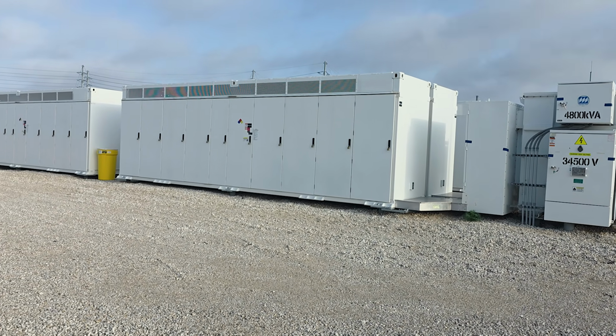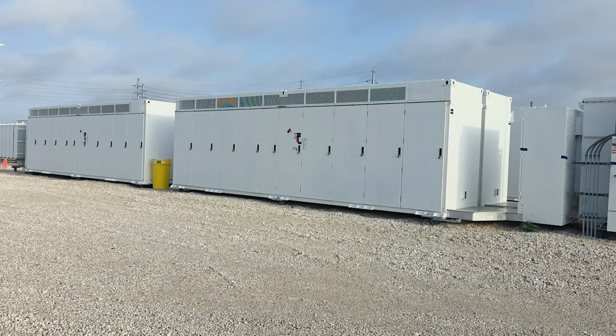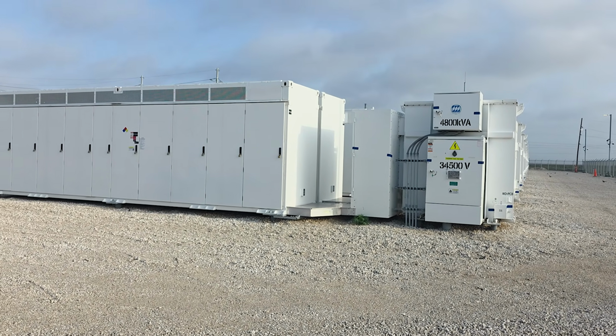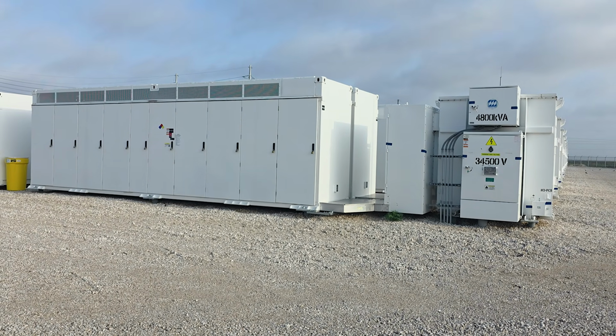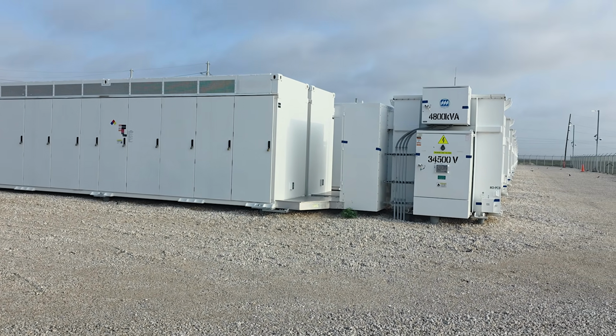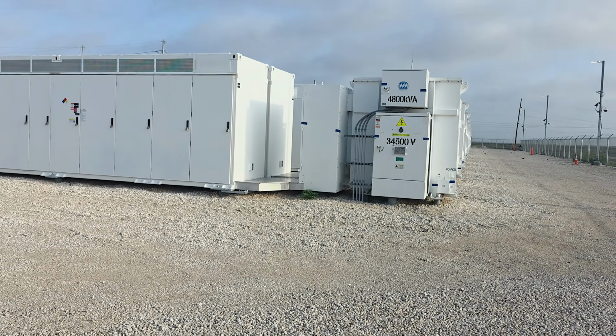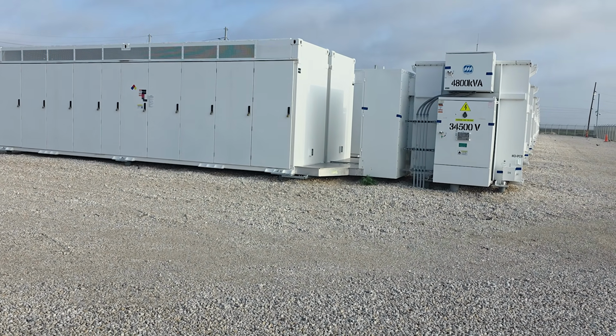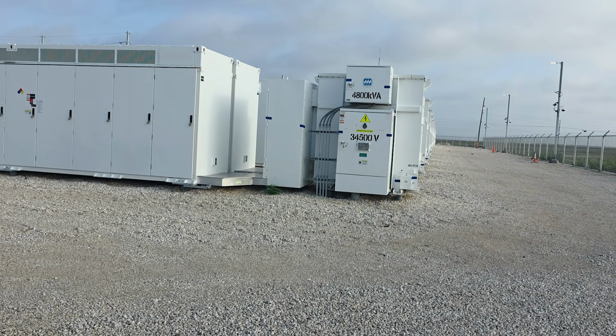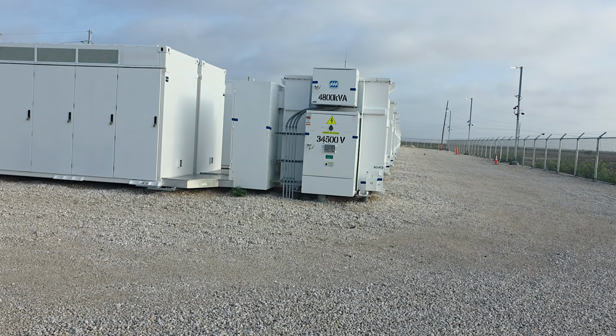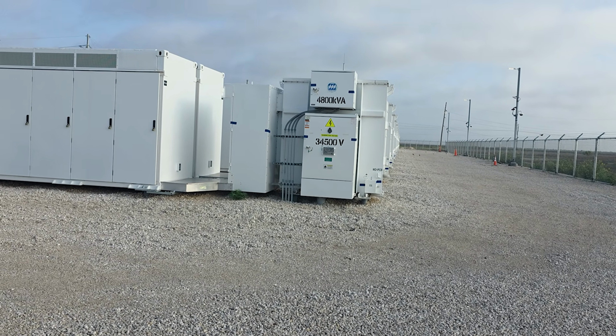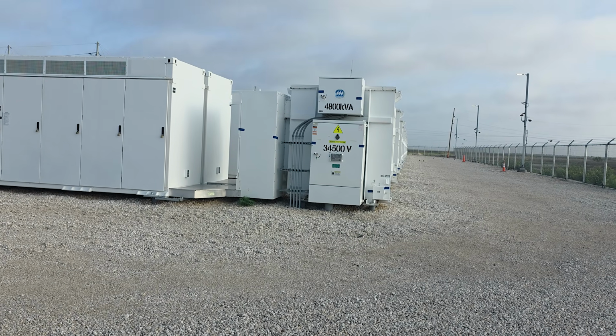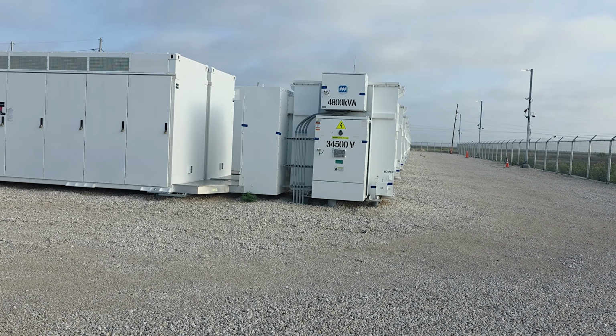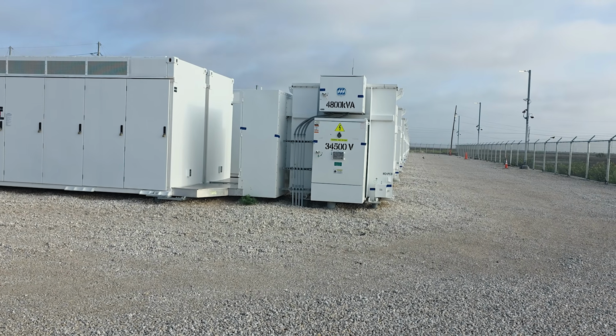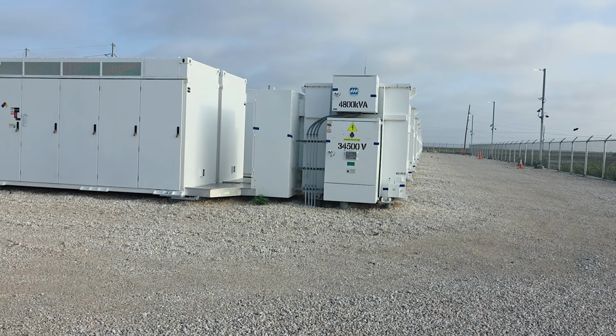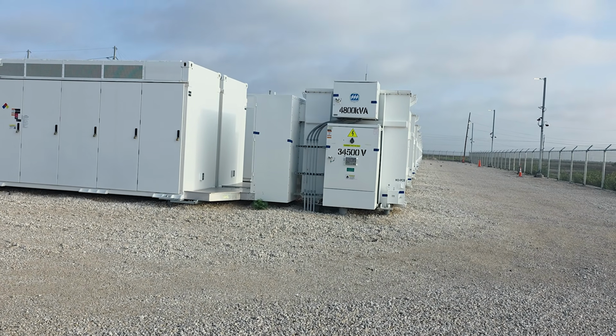You've got a battery, which you see here on the left side that you're staring at right now. And then you've got an inverter, which sometimes is external and sometimes internal to the batteries. And then you have an AC transformer that steps up whatever voltage is coming out of that inverter, coming out AC, into the transformer up to a distribution level voltage. Obviously, in this case, you can see it's 35 kV. That's pretty standard. And that's just getting the voltage up so you can get your amps down, so you can get your amps and your power to the substation without having a ton of cables, right? More amps is more cables, low amps is smaller cables. So it's kind of the most efficient way to do it.